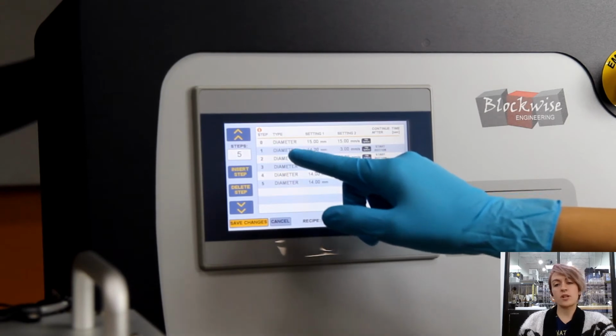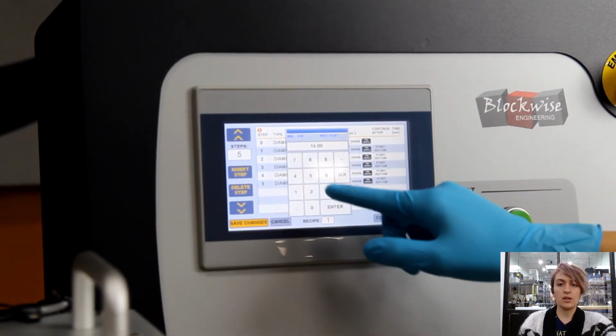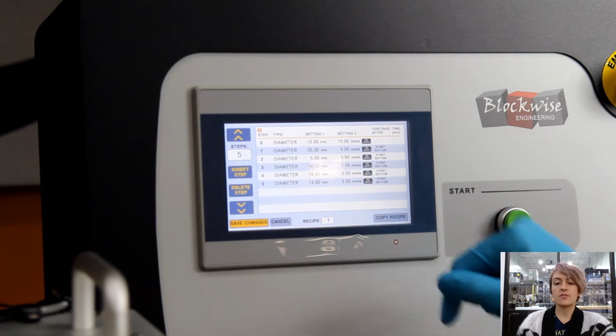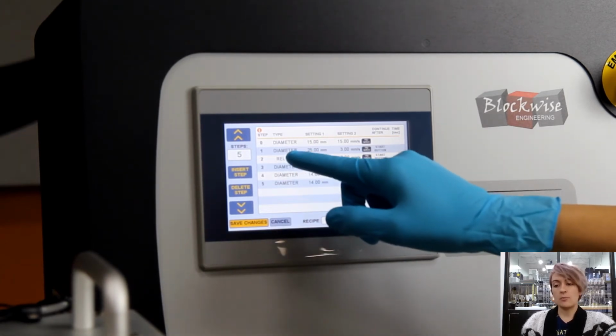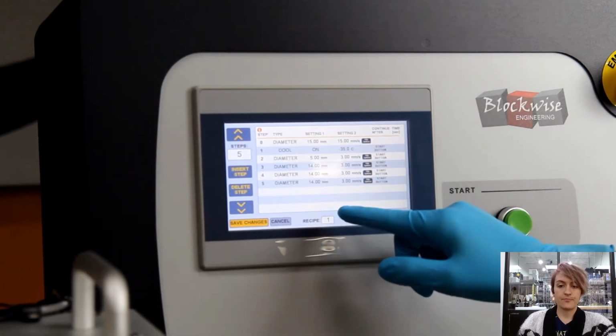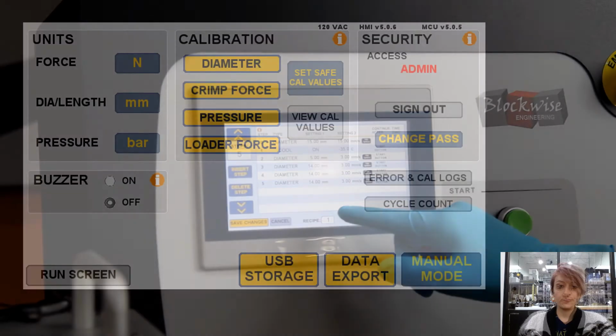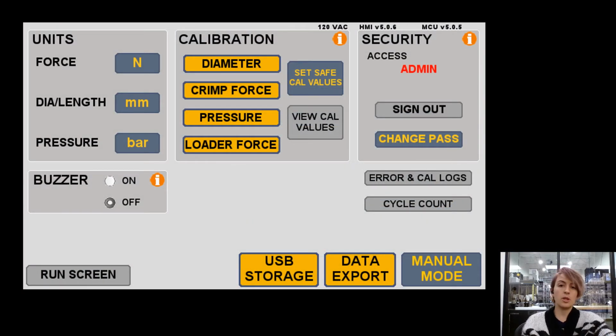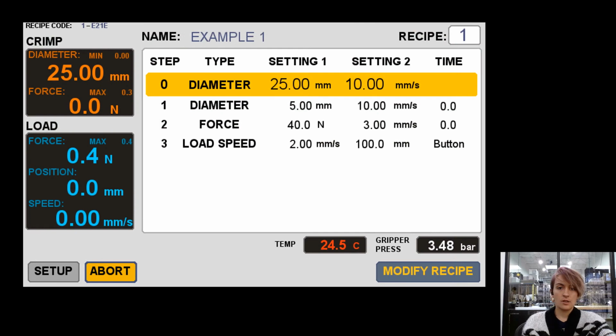For full control of the process settings, you're actually going to want to create a recipe. This will allow you to create a series of consecutive steps that fully automate the entire loading process. To create a new recipe, from the setup screen here, we'll want to push the Run Screen button down here in the bottom left-hand corner. After you push that button, it will bring you here to the recipe screen.